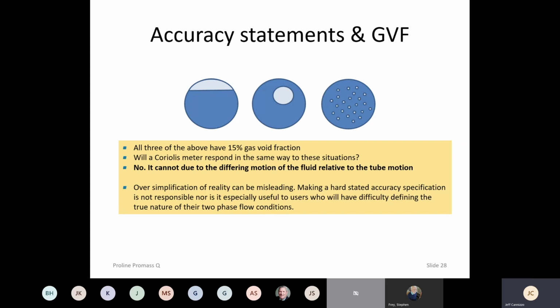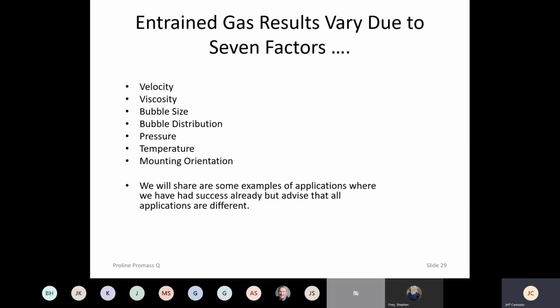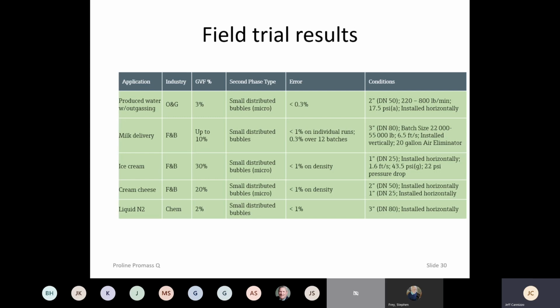And it's really tough to tell people what's going to be your accuracy, because that question always comes up. So we can't really oversimplify this. Entrained gas varies because of velocity, viscosity, bubble size, the distribution, the pressure and temperature, the mounting orientation. But the Q meter is developed to handle entrained gas very well. So if we take a look at some applications, produced water, gas void fraction of 3%, the meter handles that with error less than 0.3%.